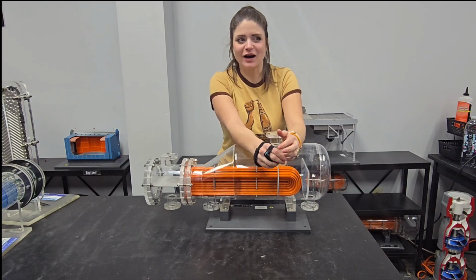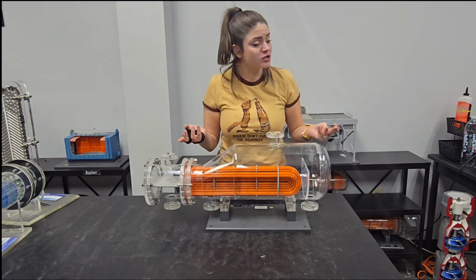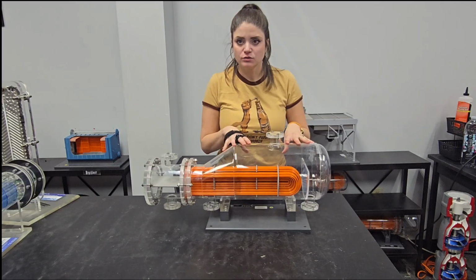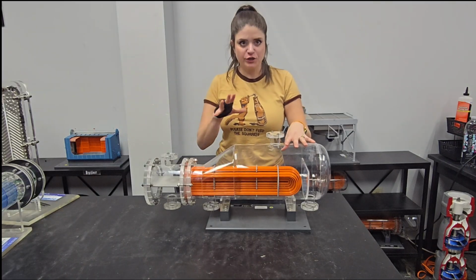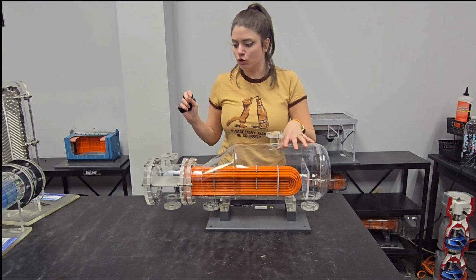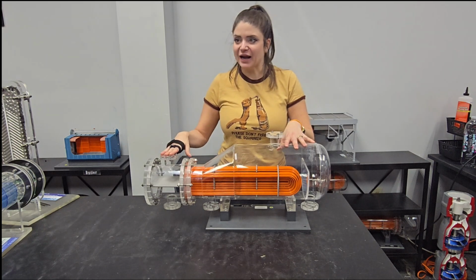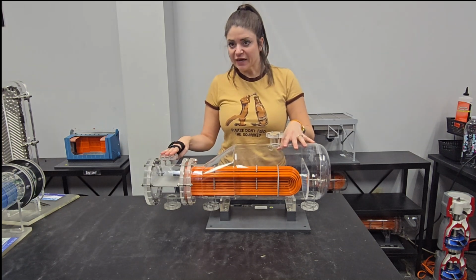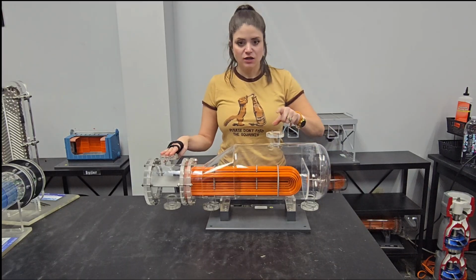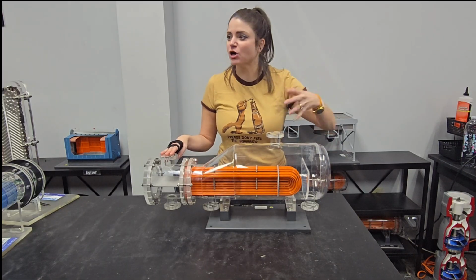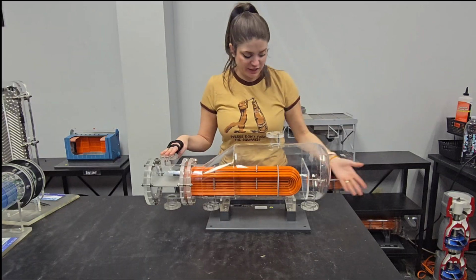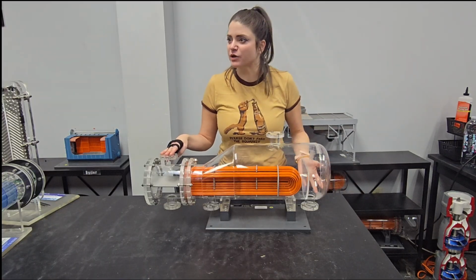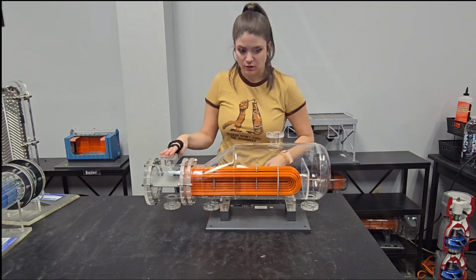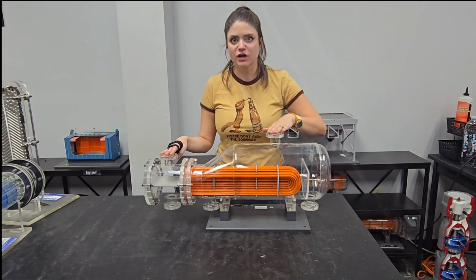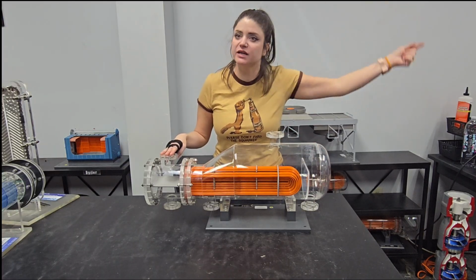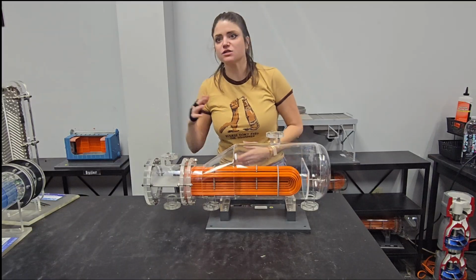You tell me. Alright, so it could also be referred to as a chiller, and so you'd have propane on your shell side. You'd be cooling your process, and as the process heat is absorbed by the propane on the shell side, it's going to boil or vaporize and get sent back to get cooled again. So your cooling process will be on your shell, coming in, overflowing, whatever doesn't flash off goes to get cold again, condensed, coming back to cool your process on your tube side.